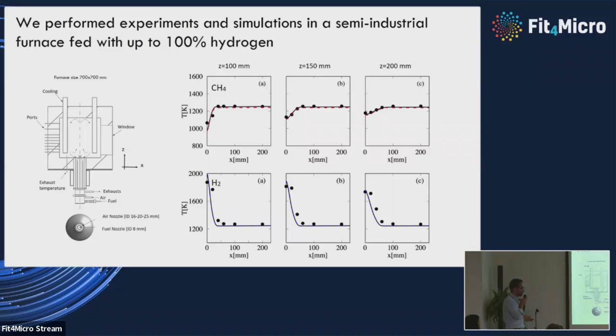...you are not working in flameless conditions anymore. You have very significant temperatures, reaching almost 2000 Kelvin, with a very strong rise in temperature. So the system, despite using a flameless furnace and flameless burner, is not actually operating in flameless conditions. This is also visible if you look at chemiluminescence—the spontaneous emissions from the flame.